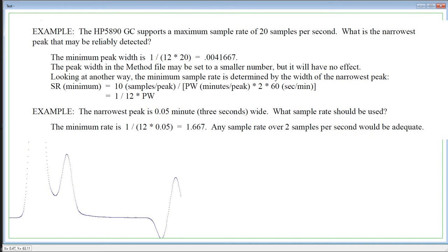Looking at another way, the minimum sample rate is determined by the width of the narrowest peak. Sample rate minimum equals 10 samples divided by peak divided by peak width minutes divided by peak multiplied by 2 multiplied by 60 seconds divided by minutes equals 1 divided by 12 asterisk peak width.